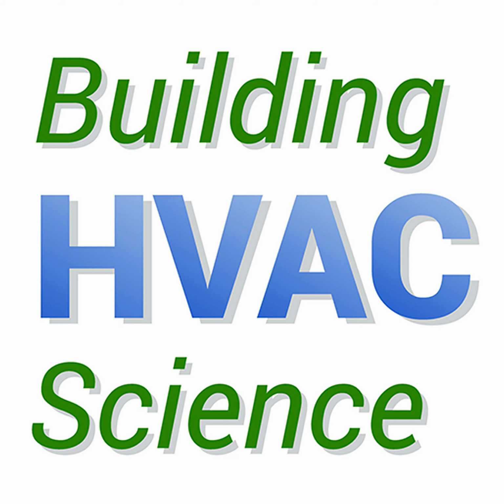So -40 is basically the temperature you get down to. If you happen to get that cold, what would happen is, again, it would crystallize out. And then as it started warming up again, it would turn back into a liquid. So as long as you don't try to operate it at -40 or below, you should be fine. And pretty comfortable that's not going to happen. Not unless we get it up pretty far north into Canada. Maybe northern Michigan or Minnesota might see some of those -40 periodically, but not very often.